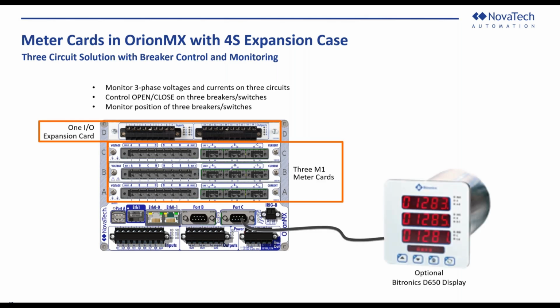We also want to emphasize that there is an optional display that can be provided. This is the D650 Bitronics display. This is actually a DNP or Modbus client. So the display itself can query any IED, including the Orion, and any data value inside the Orion can be read by the display, scaled and displayed as shown.